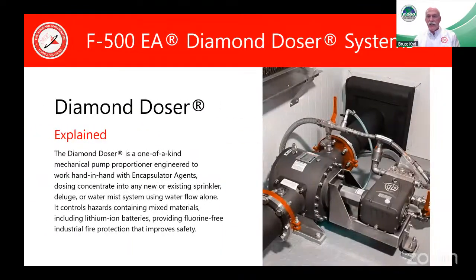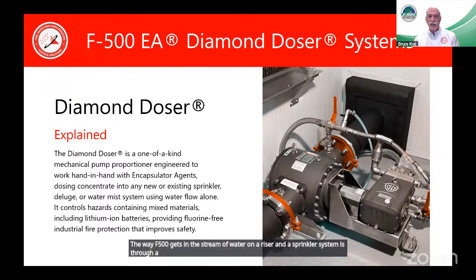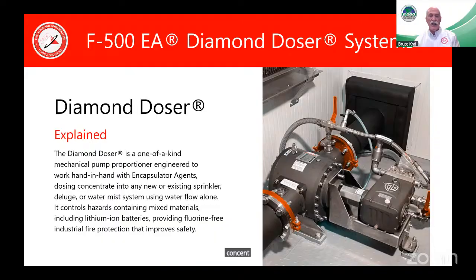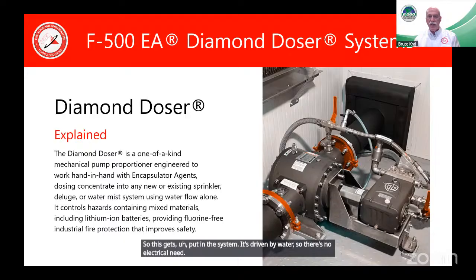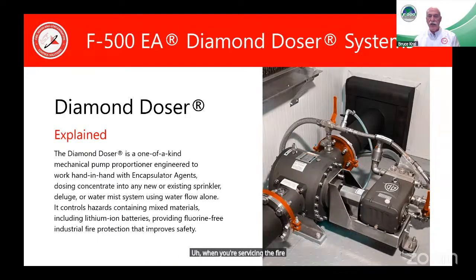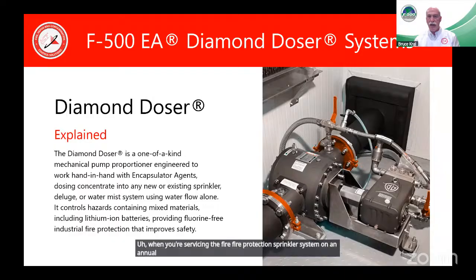The way F500 gets in the stream of water on a riser and a sprinkler system is through a diamond doser. It's a mechanical pump proportioner, delivering a precise 3% concentration on the discharge of the water F500 mixture. So this gets put in the system. It's driven by water, so there's no electrical need. When you're servicing the fire protection sprinkler system on an annual basis, there's a bypass valve so you don't discharge F500 unnecessarily.